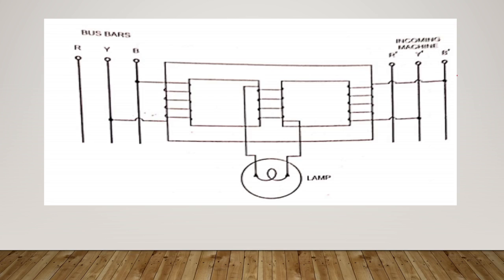But in practice, it is very difficult to adjust the speed of the incoming machine closely enough to stop the synchroscope pointer in the vertical position. So in that case, the speed of the incoming machine should be adjusted as closely as possible and the paralleling switch closed just before the pointer reaches the vertical position when traveling in the fast direction.